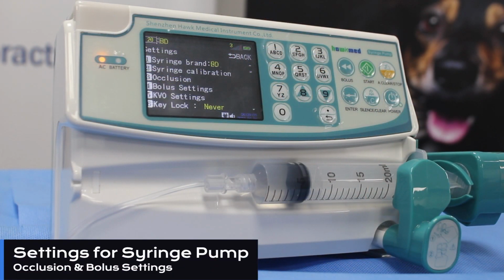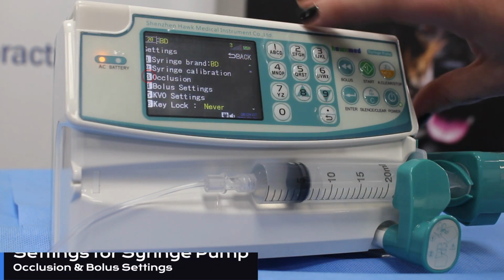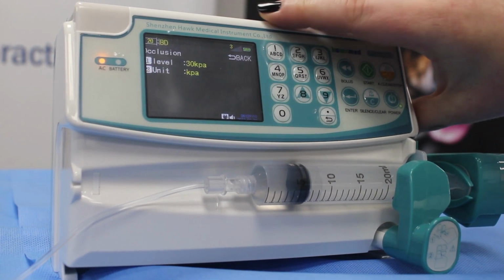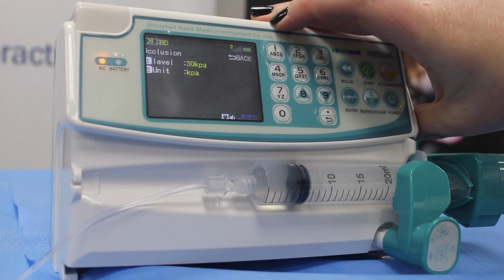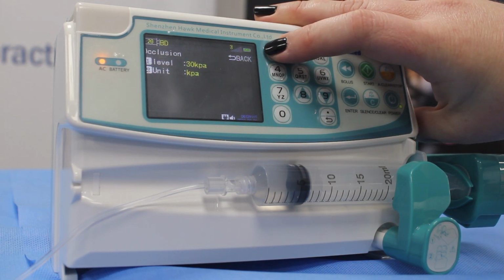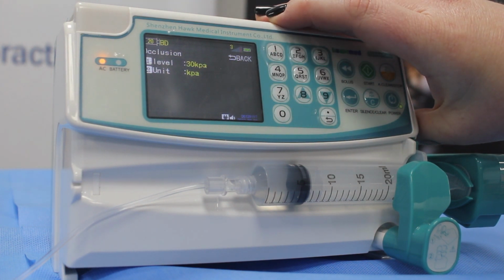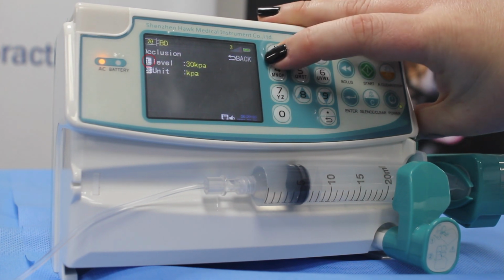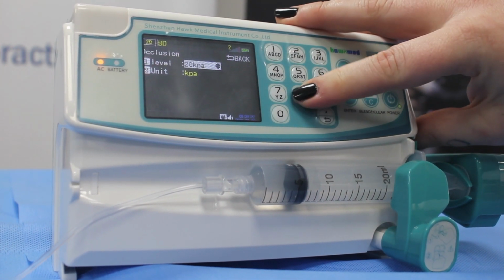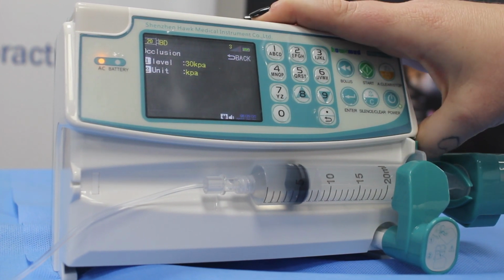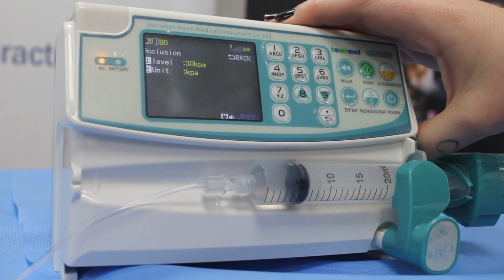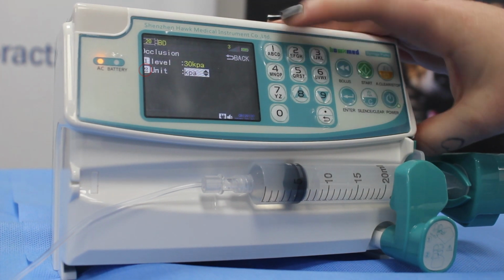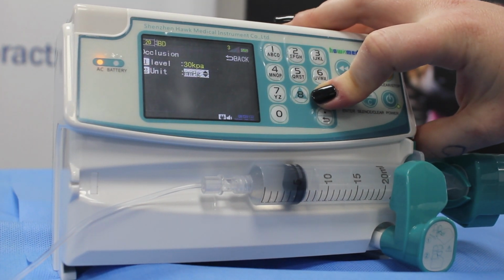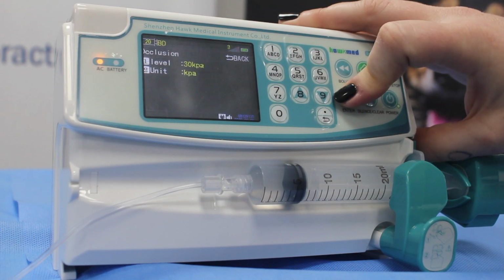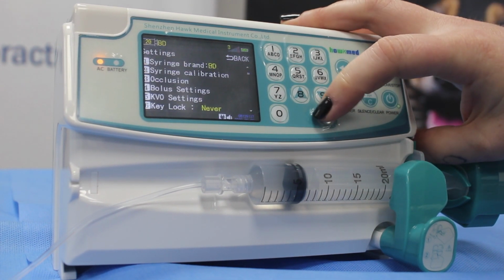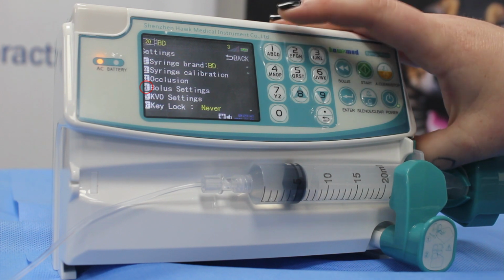Your occlusion sensitivity can also be adjusted under number 3 on the screen. Here we have the level, so the amount you would like it to alarm at, which is currently 30 kPa, which we can adjust by just pressing the corresponding number, adjusting as required, and pressing enter to confirm. We can also adjust the unit of our measurement with number 2, using 8 and 9 to adjust, and pressing enter to confirm. Going back again, our next setting here is for the bolus settings.